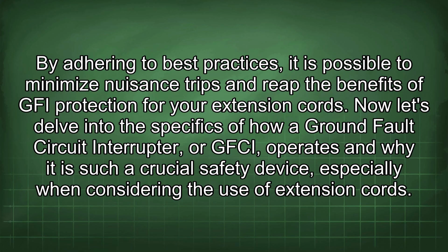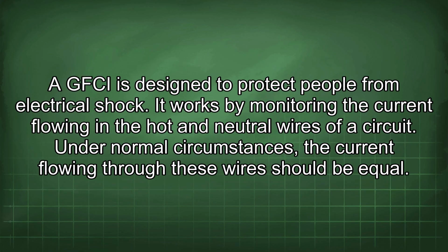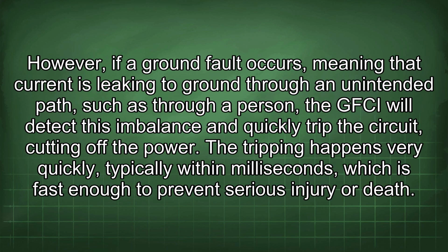Now let's delve into the specifics of how a ground fault circuit interrupter, or GFCI, operates and why it is such a crucial safety device, especially when considering the use of extension cords. A GFCI is designed to protect people from electrical shock. It works by monitoring the current flowing in the hot and neutral wires of a circuit. Under normal circumstances, the current flowing through these wires should be equal. However, if a ground fault occurs, meaning that current is leaking to ground through an unintended path, such as through a person, the GFCI will detect this imbalance and quickly trip the circuit, cutting off the power. The tripping happens very quickly, typically within milliseconds, which is fast enough to prevent serious injury or death.